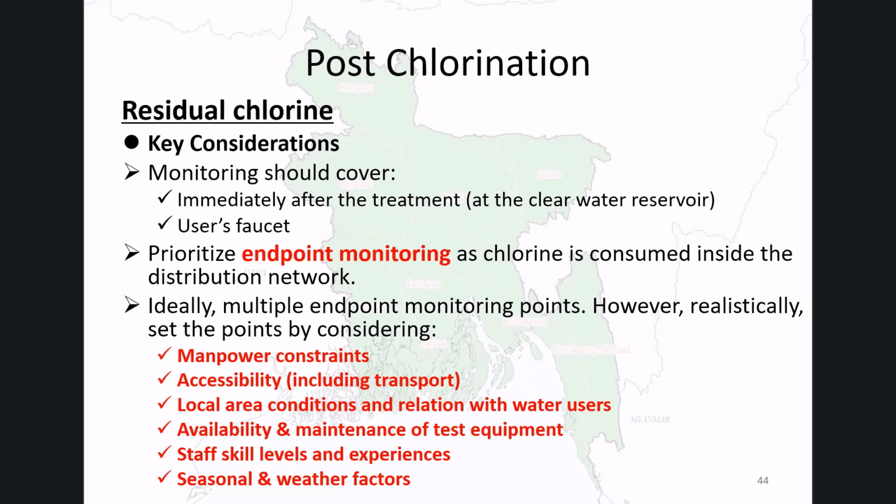Here are some consideration points on the post-chlorination. 1. Monitoring residual chlorine must cover two important points. One is immediately after treatment at the clear water reservoir. The other is at the user's faucet.